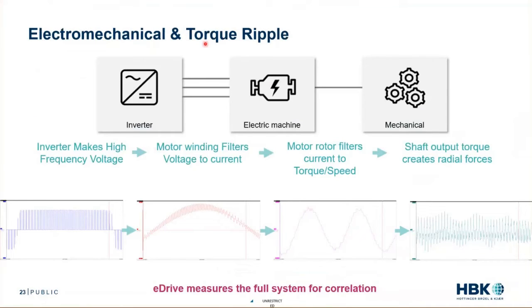We are electromechanical, and this doesn't show up as good as I hoped. I'm sorry about that, but we will record your high frequency inverter at a high enough rate where you can understand all those PWM switches. We'll then record the current at that high rate so you can see the current harmonics and start to tie that back to maybe torque ripple or vibration. We record the torque at up to 6 kilohertz, and if you have a higher bandwidth torque sensor, we could record at a higher rate as well.